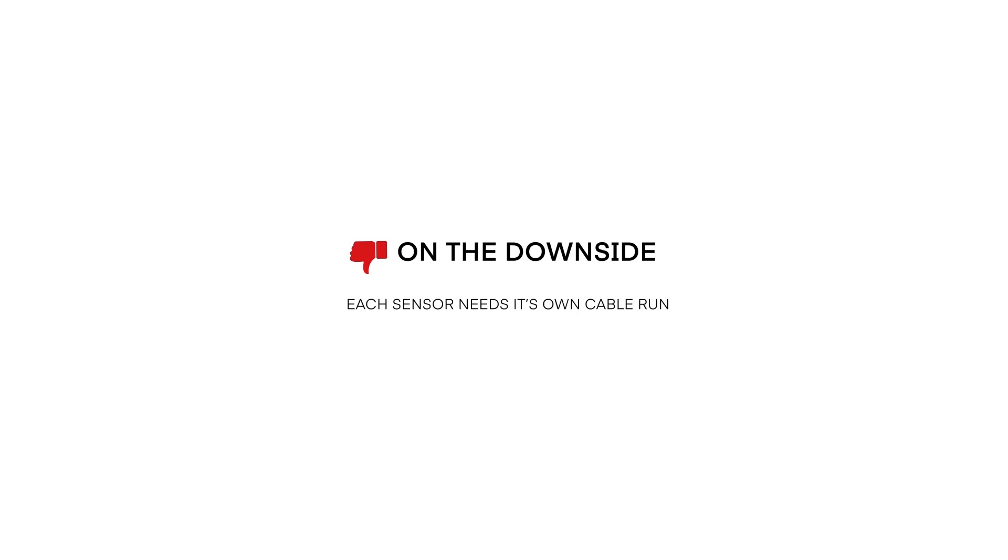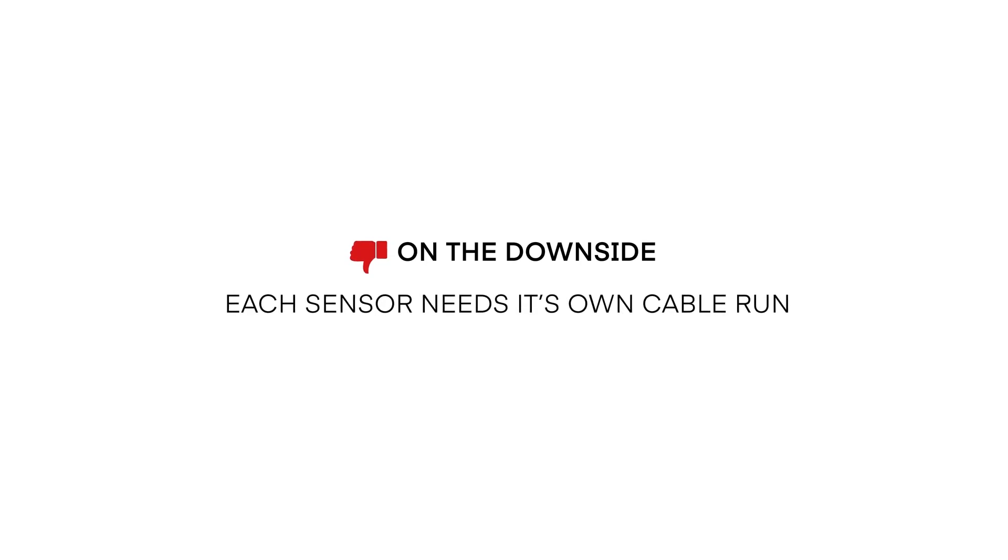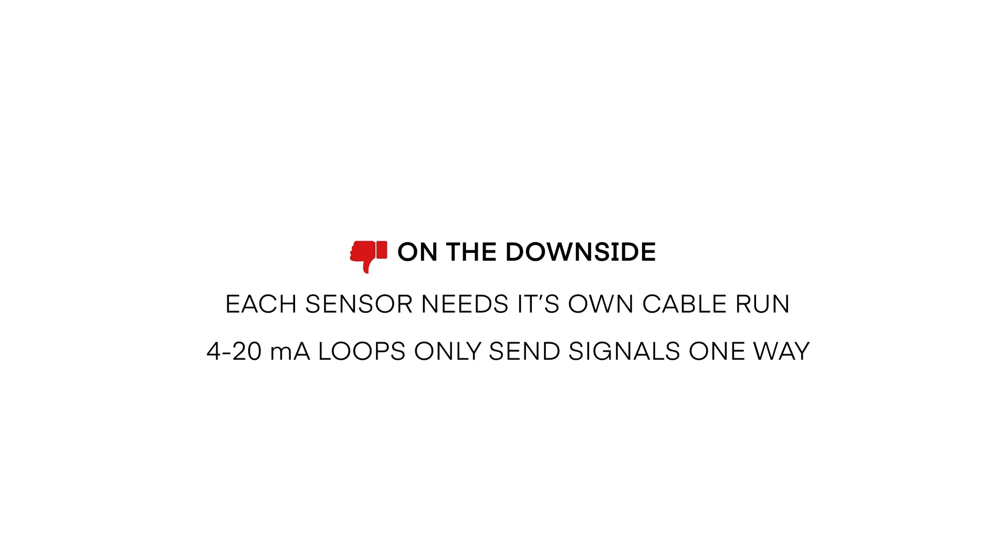On the downside, each sensor in your system will need its own cable run to the power supply and receiver, and each 4 to 20 milliamp loop only sends information one way, either to or from the instrument.